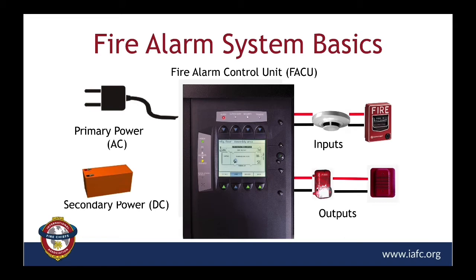Input devices, number two, are called initiating devices, and they detect a fire and send signals to the fire alarm control unit, which determines if an alarm condition is needed and sends signals to the output devices. Number three, the output devices, are called notification appliances, and obviously they provide occupant notification. And lastly, all fire alarm systems are required to have a primary and secondary power supply to operate the system under normal conditions and during emergency situations.